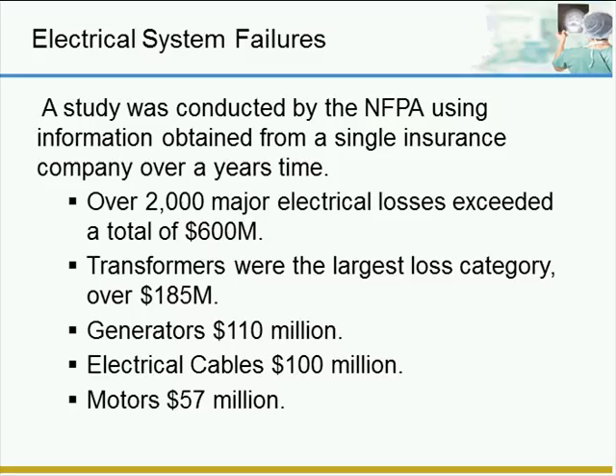Transformers are usually severely costly failures. Generators and electrical cables are just over $100 million each, and motors were at $57 million. The causes of these losses included overloaded circuits, overheating, foreign objects, long-term deterioration, dirty power, improper system designs, and the big one is the lack of maintenance. Again, electrical system failures can be catastrophic and can be cascading.